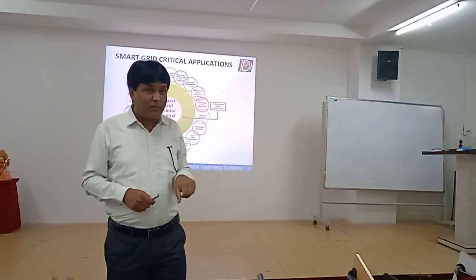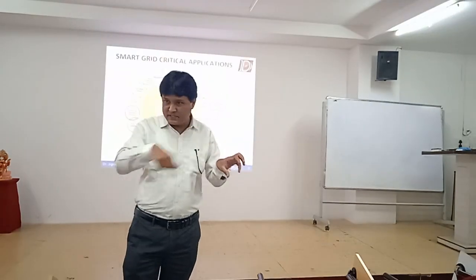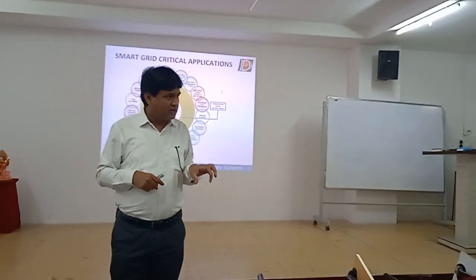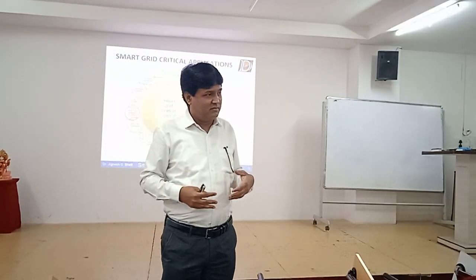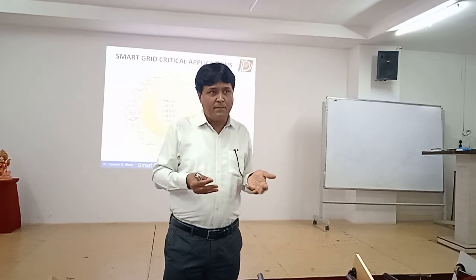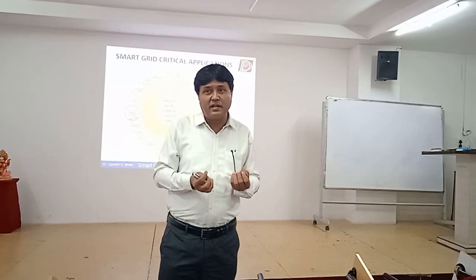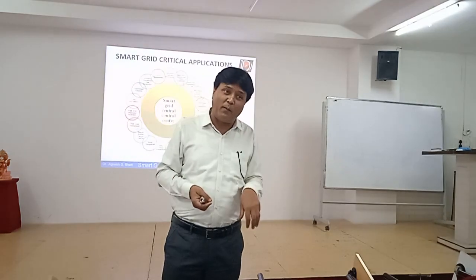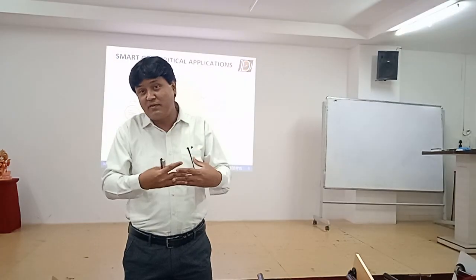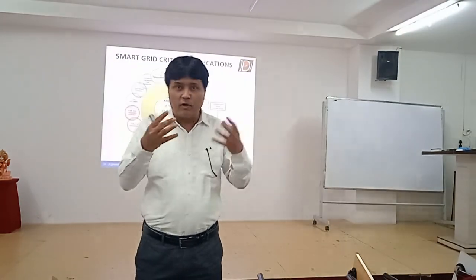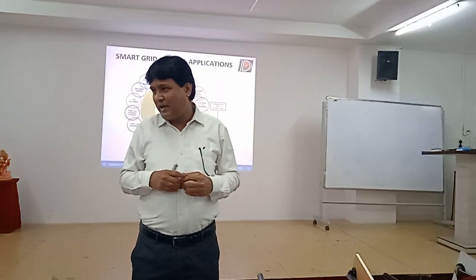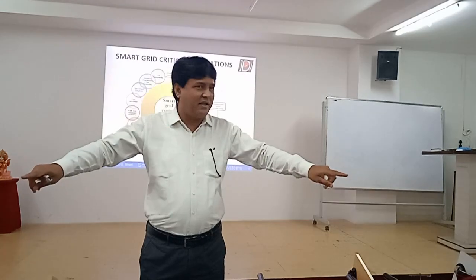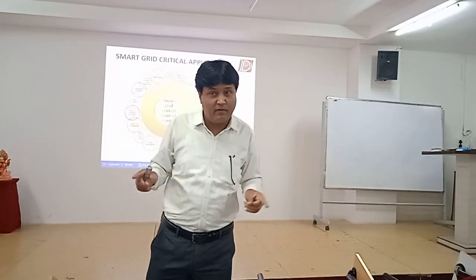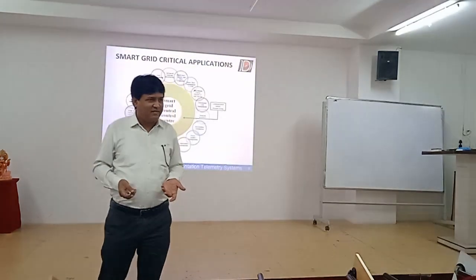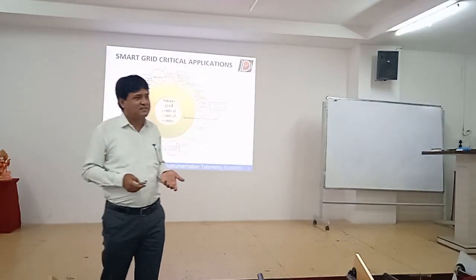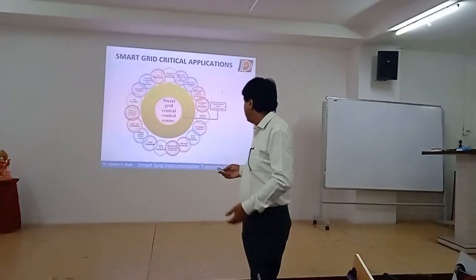When they are using their own power plant, they are also getting grid supply from the state electricity board or other service providers. Now, how to match that power? Because everything cannot be produced in-house, so some power you take from the utility company and some you produce yourself. If they are not matching in terms of frequency, that area will have a lot of disturbance and collapsing. And if that spreads to nearby areas like Valsad and Navsari, you will have a cascade tripping that you cannot stop. It is so fast, so outage management is a very key area here.